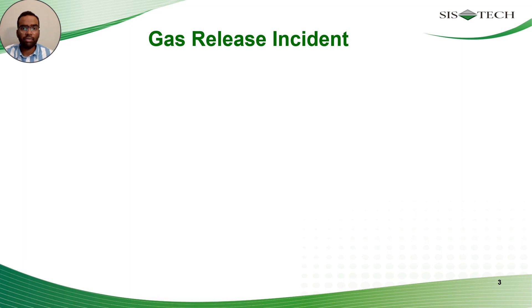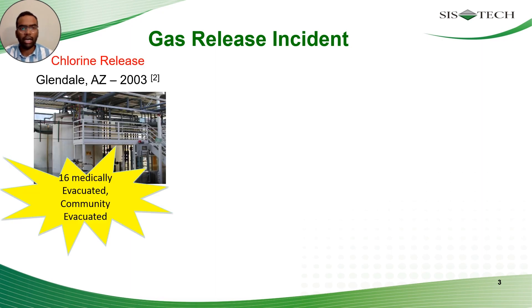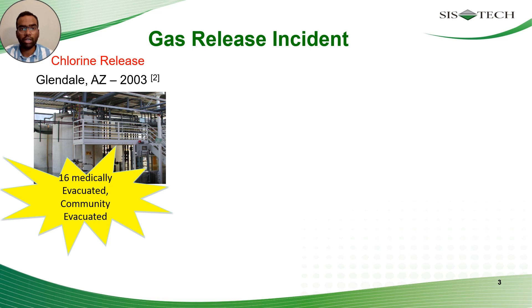Let's start with the incident. This is a gas release incident that happened at DPC Enterprises in Glendale, Arizona. They had a chlorine release which led to 16 medical evacuations and nearby community evacuations. This facility repackaged chlorine from rail cars to small containers. The chlorine scrubber at this facility had two purposes: one is to capture all the chlorine vented in the repackaging operation, and second is to produce a sellable bleach. The operating conditions for these two purposes were not identical, and operating the chlorine scrubber as both a safety device and a by-product generation unit required utmost care and had an increased likelihood of toxic release.